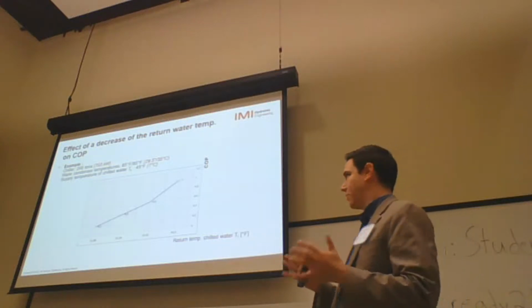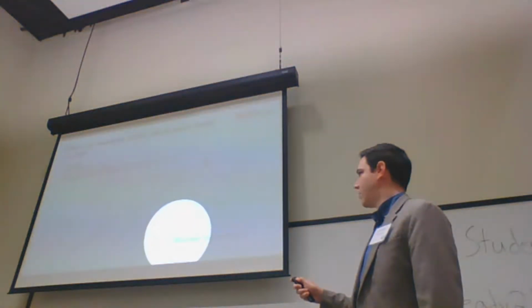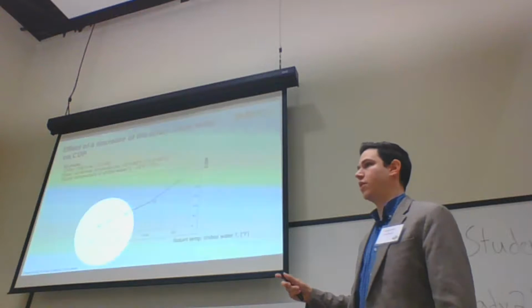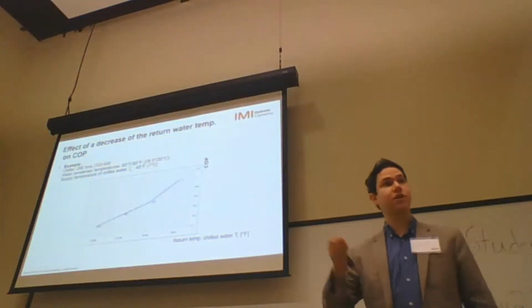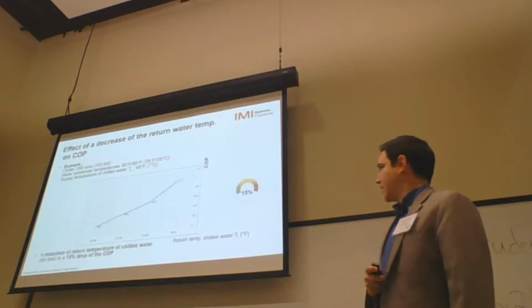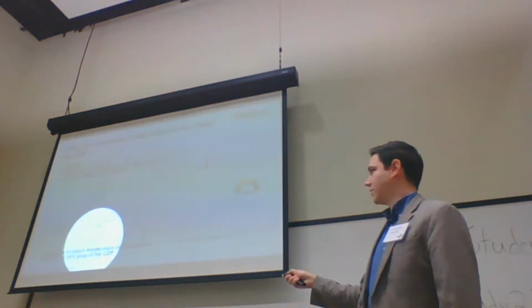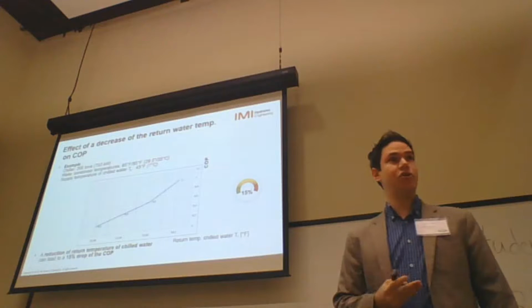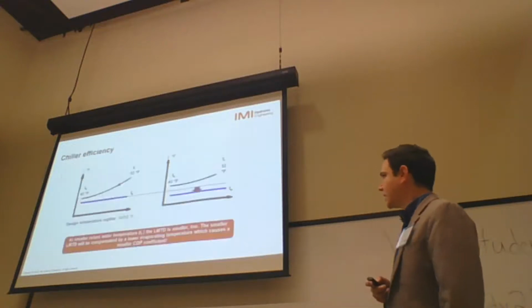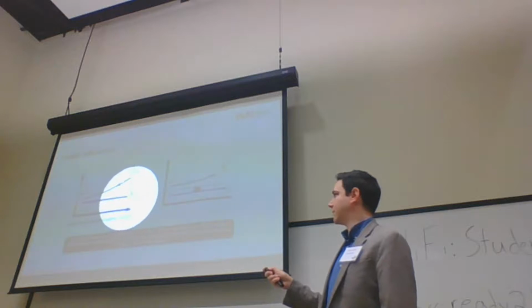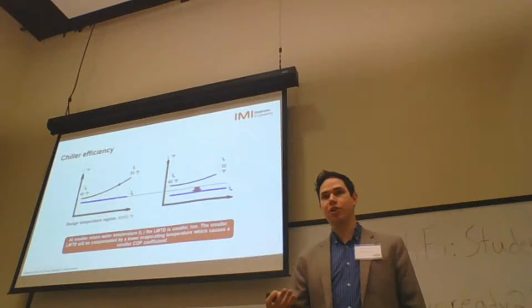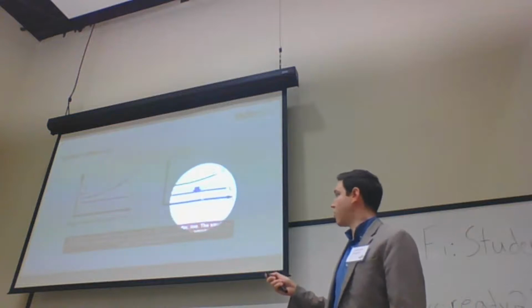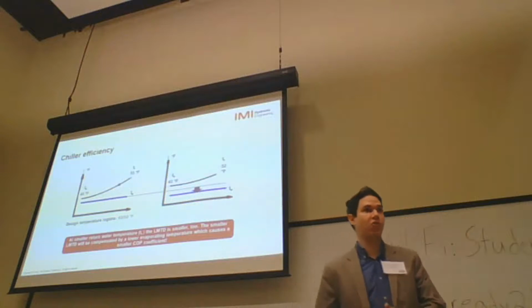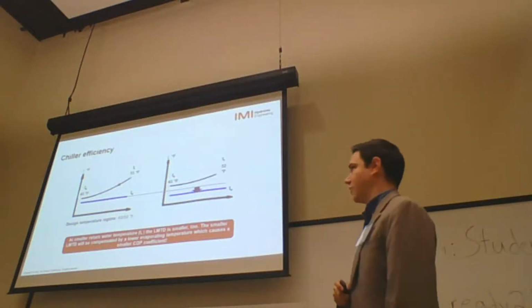The biggest picture, the biggest point for us to understand on this graphic is, as soon as my return temperature, chilled water, starts getting back lower from my system back to the chiller, you start to decrease the chiller's performance. And in this example that I'm talking about, close to 4 degrees, 5 degrees lower than the design condition, you're losing 15% of the chiller's efficiency. The reason that happened is when you have the design condition, 45 degrees to 55 in this example, this dark blue line is the evaporating temperature inside the chiller. If my return temperature, chilled water, instead of 55, starts returning to 52, the chiller needs to drop the evaporating temperature, and that's why it's working with a lower performance, decreasing the COP of the chiller.